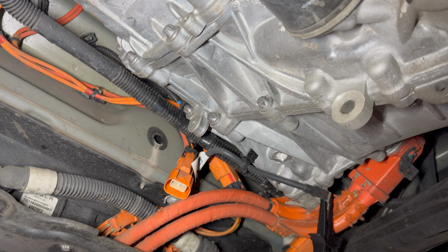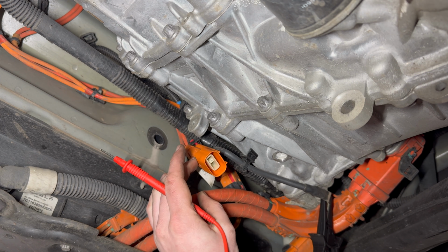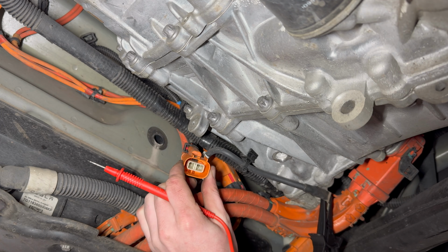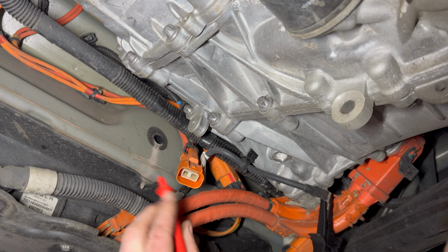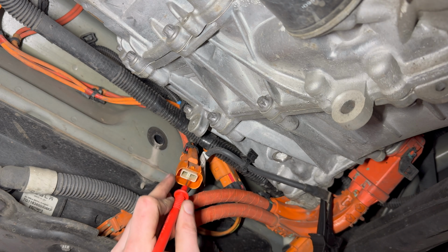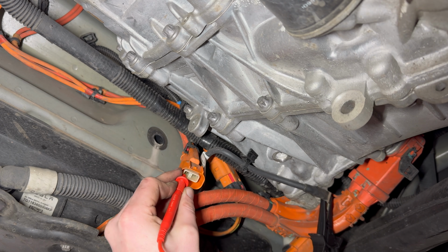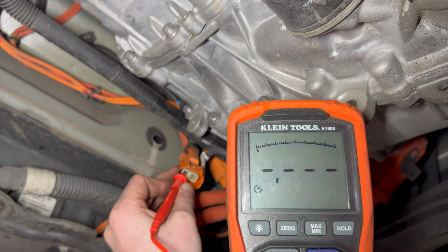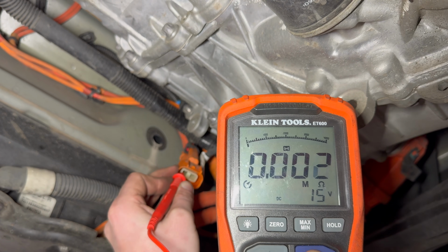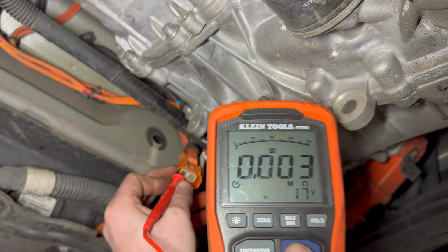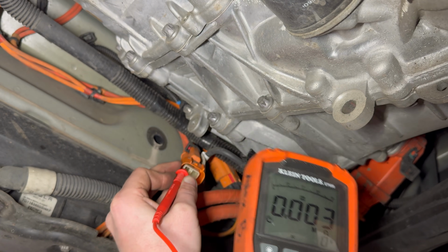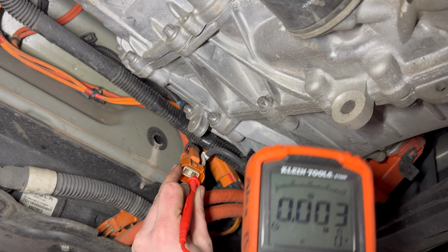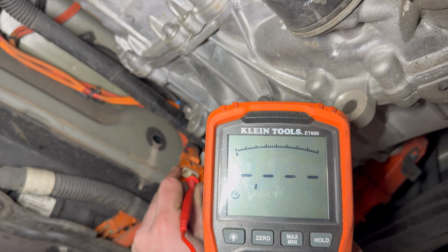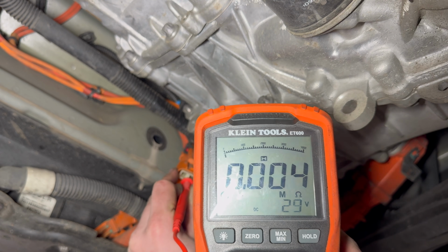I'm just going to put it on the motor right there, since this is a ground shielded connector. I'll go to either one of these two pins and hit test. Yep, you can see we've pretty much got a dead short there, so that definitely indicates a loss of isolation.